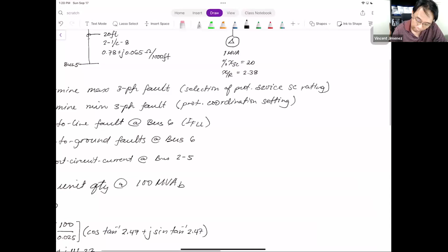Pwede natin paghiwalayin yung R and X using the X over R ratio. So we have here cosine of arctangent 2.38 plus J sine of arctangent 2.38. And this will give us the per unit impedance of our contributing load as 7.75 plus J18.44. So we just need to plug in the values here.